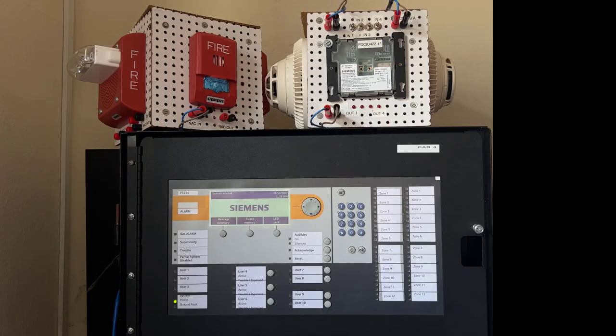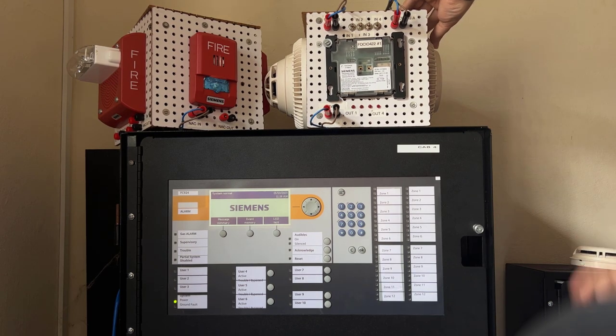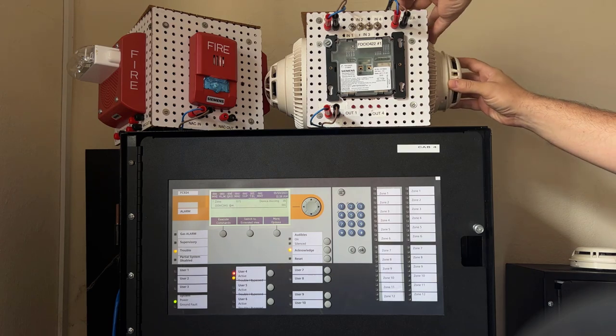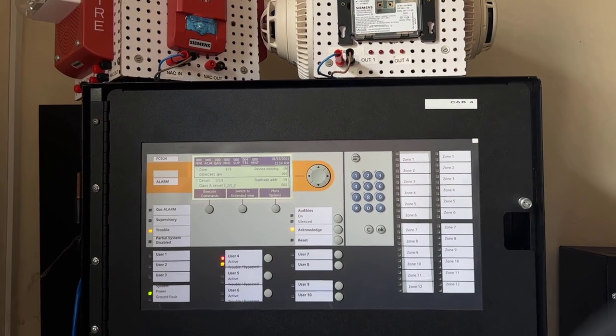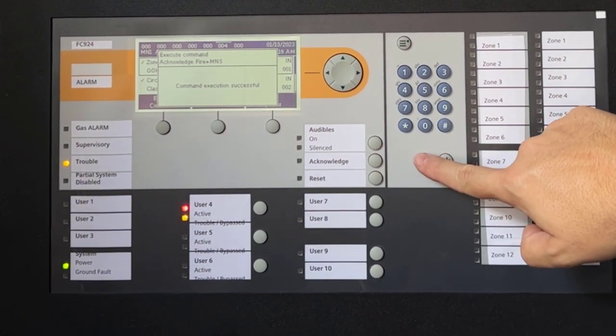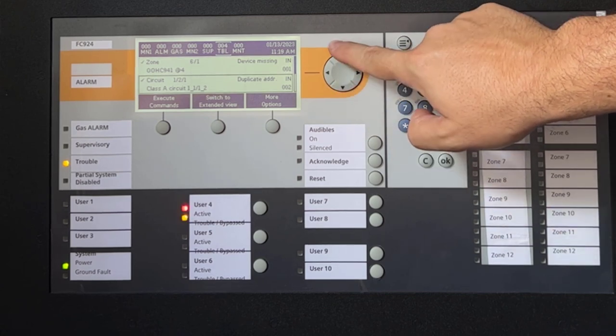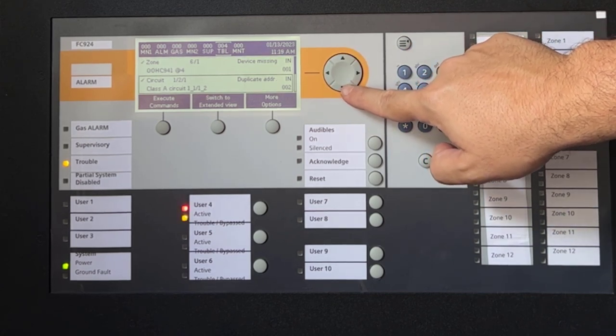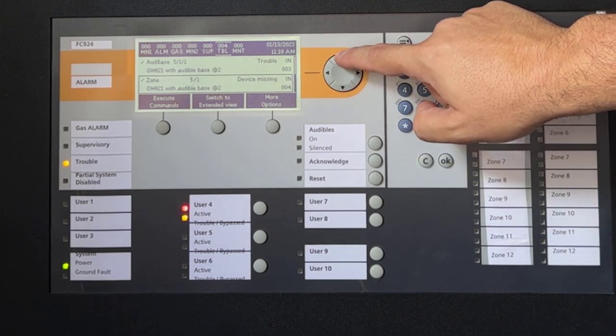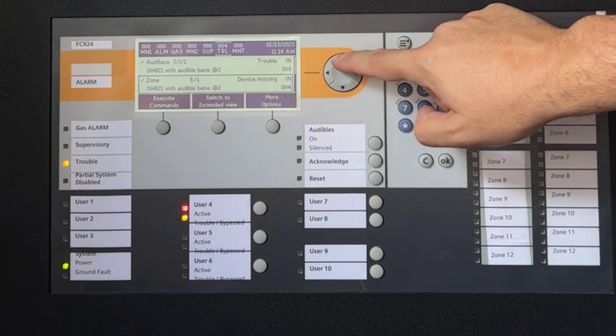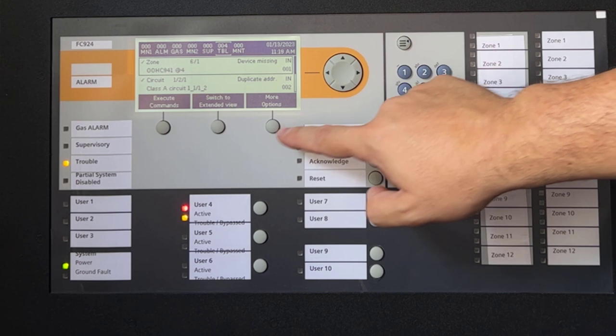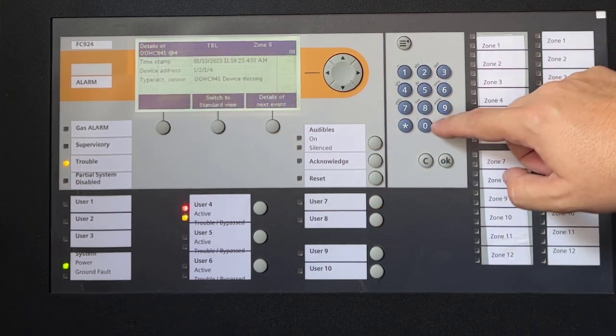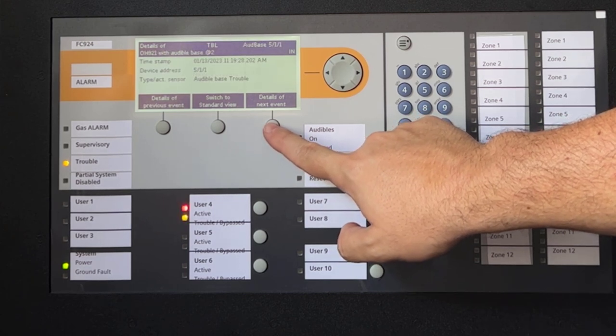In this next scenario, I created a duplicate address condition on the loop, by repeating address 2. As you can see, I have a device missing trouble for my detector 4 and a duplicate address trouble on my panel, among others for the Audible base. These events, along with the address showing in the customer texts, helps the technician piece together what is happening and fix the problem. The new device with address 2 was not programmed so there is no customer text associated with it. If you do not have the addresses easily available in the customer text, the troubleshooting process may take longer.